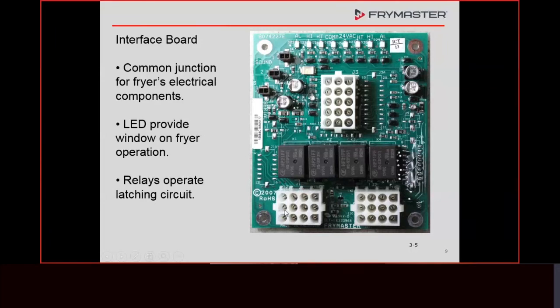Taking that plug from the back, you turned it upside down to put it on the front. So whereas this here is now pin number 1: 1, 2, 3, 4, 5, 6. Before it was different. Pins 6 and 9 are the two you would check for the high limit and drain switch—I'll show you that on the wiring diagram.